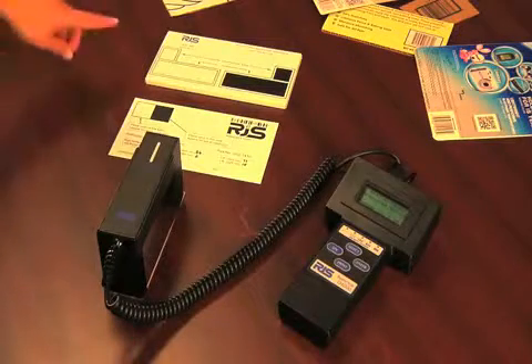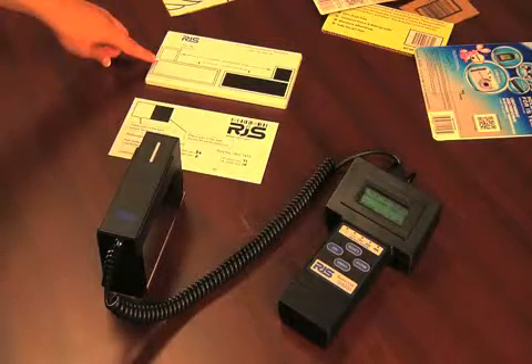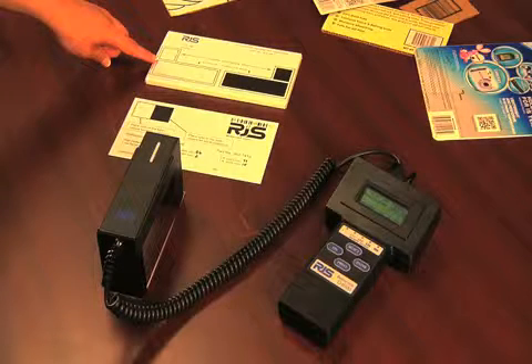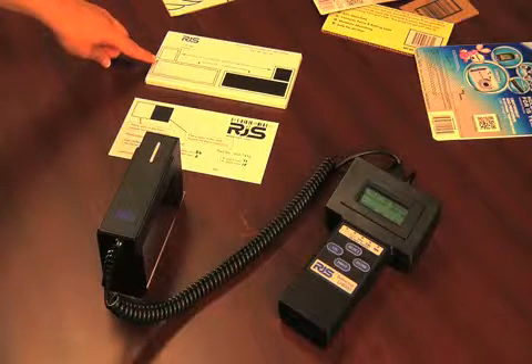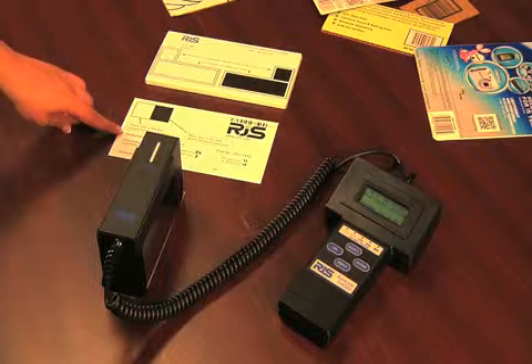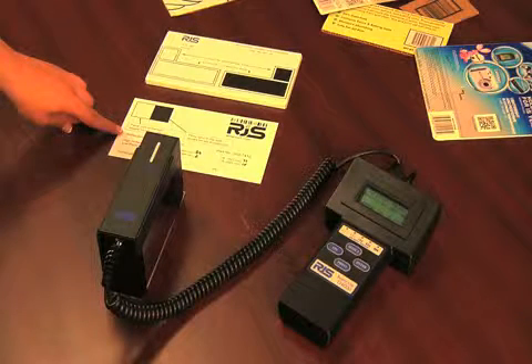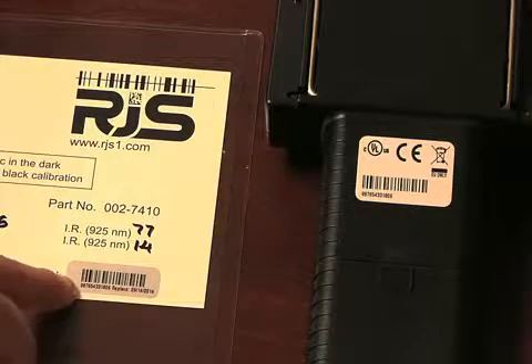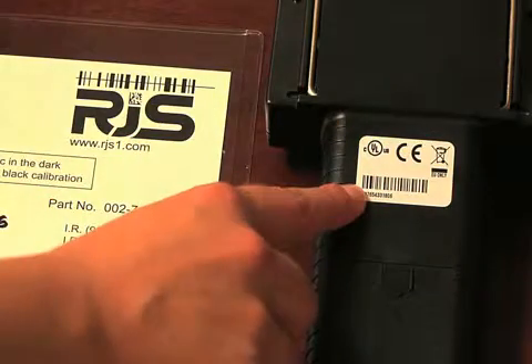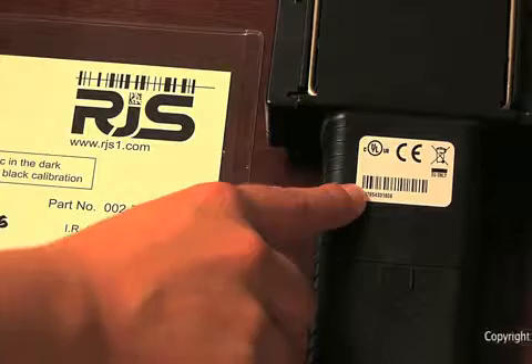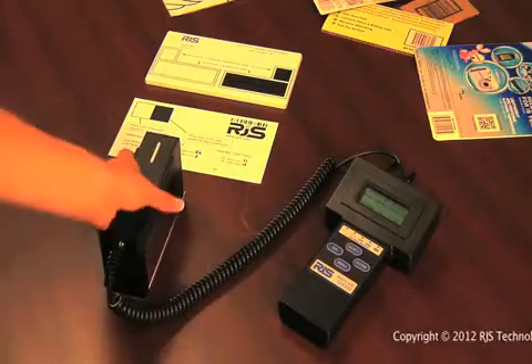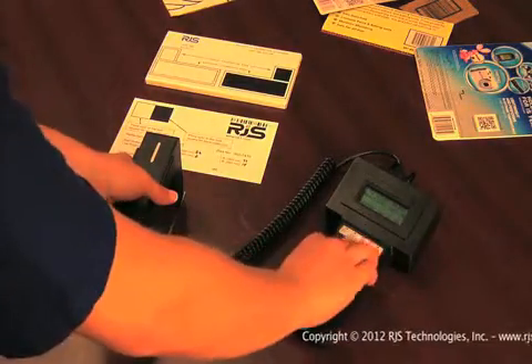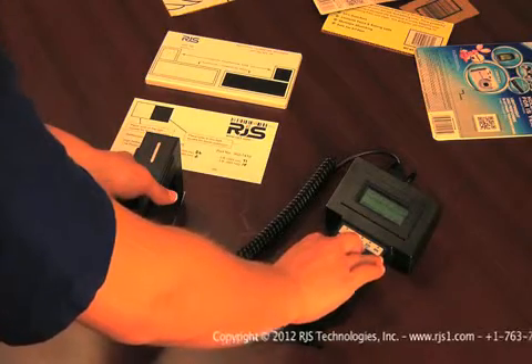Older units will have a metal calibration plaque like this, while any units manufactured since 2010 will have a film calibration plaque like this. Either plaque will work, but it's very important to only use the calibration plaque with a serial number that matches the serial number on your barcode verifier. This is important because each barcode verifier is set to the specific reflectance values on the matching calibration plaque.